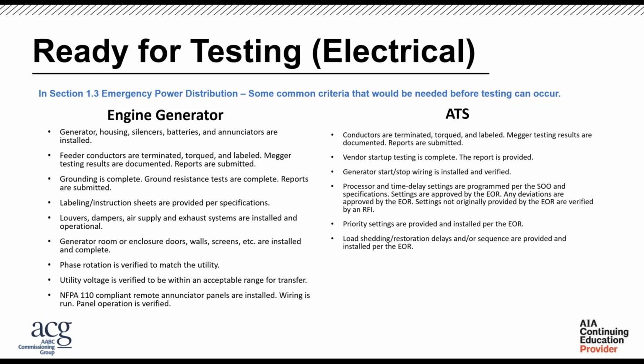And then, of course, you have your transfer switch. You want to make sure that vendor startup is completed. You want to make sure it's connected to your generator. All that wiring is connected. That when you're sending your start-stop signal, they're coordinated correctly. You want to make sure that the time delay has already been programmed. There have been multiple instances when I'm testing transfer switches that it is still on that default, probably 30 minutes. And that's not always what's needed, especially if you have multiple transfer switches where you might want different time delays, for life safety coming back versus standby power. So these are some of the bigger things that you want to make sure you're looking at.